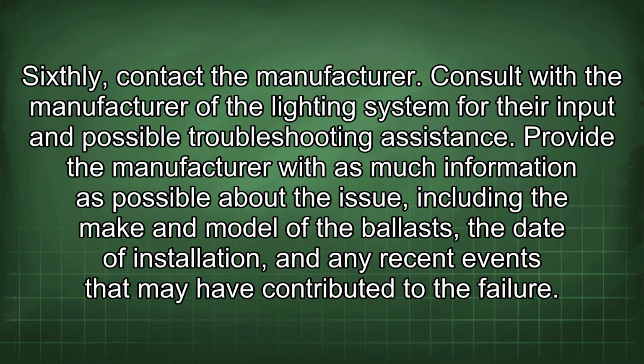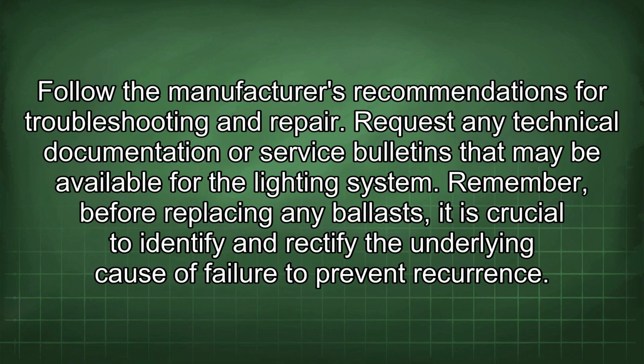Sixthly, contact the manufacturer. Consult with the manufacturer of the lighting system for their input and possible troubleshooting assistance. Provide the manufacturer with as much information as possible about the issue, including the make and model of the ballast, the date of installation, and any recent events that may have contributed to the failure. Follow the manufacturer's recommendations for troubleshooting and repair. Request any technical documentation or service bulletins that may be available for the lighting system. Remember, before replacing any ballast, it is crucial to identify and rectify the underlying cause of failure to prevent recurrence.